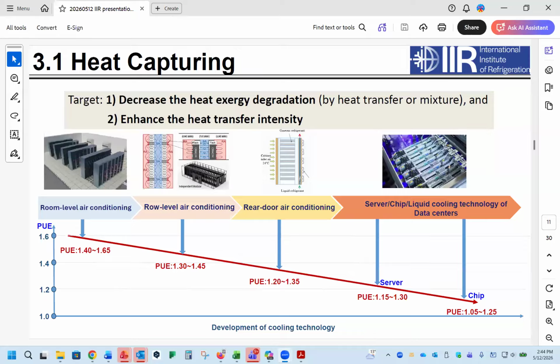If we want to decrease PUE further, liquid cooling systems appear. With server-level cooling, PUE can decrease to 1.15 to 1.30. With chip-level cooling, PUE can decrease to 1.05 to 1.25.